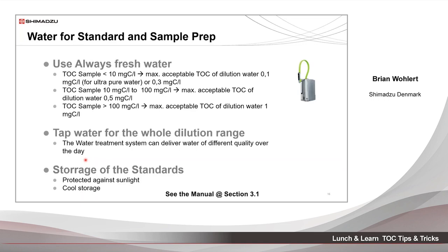We see at a lot of customer sites that the water can vary over the day. So please tap the water in one pool for the whole range of standards and control samples you're preparing. When you store the standards, please always do it in the refrigerator and protect the standards against light.